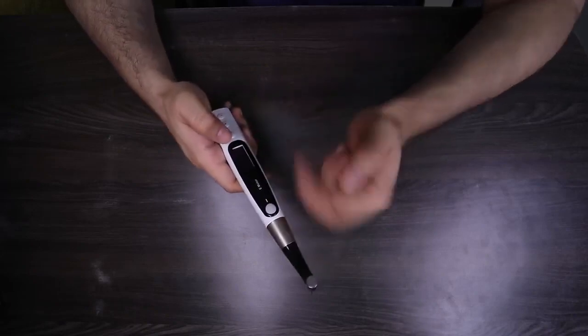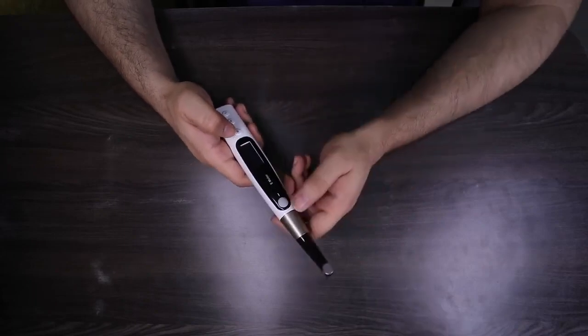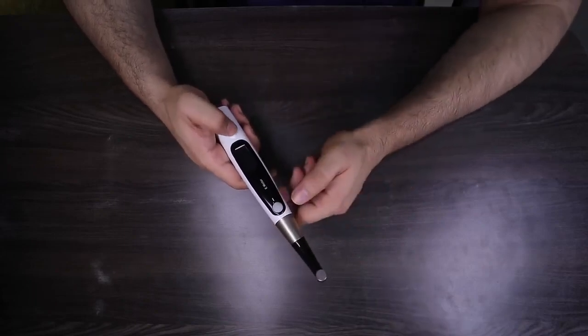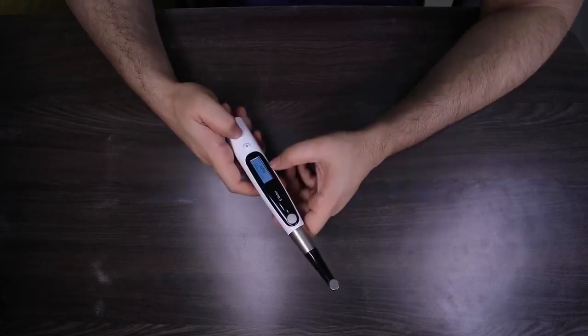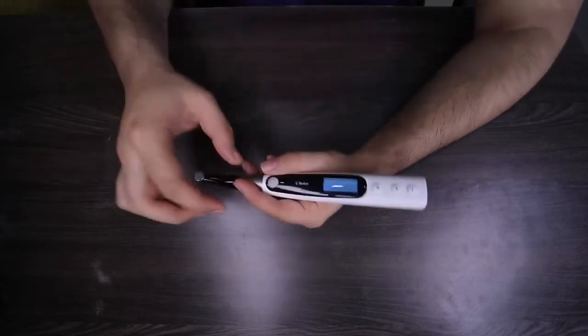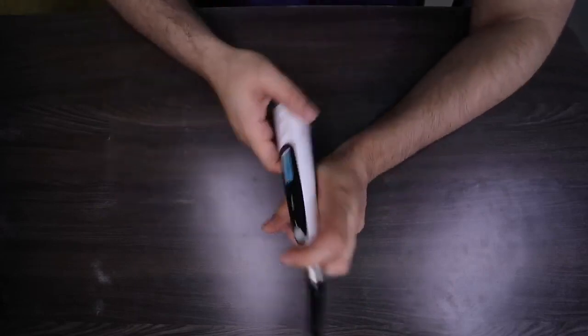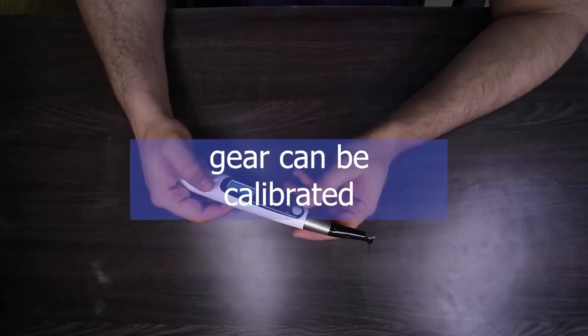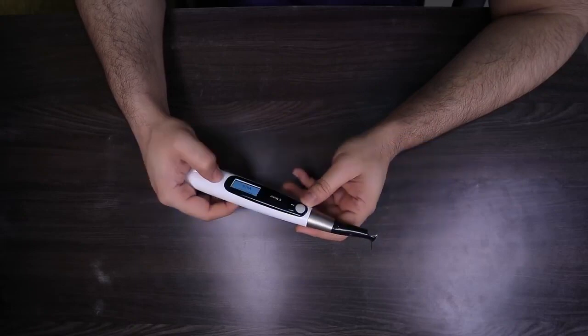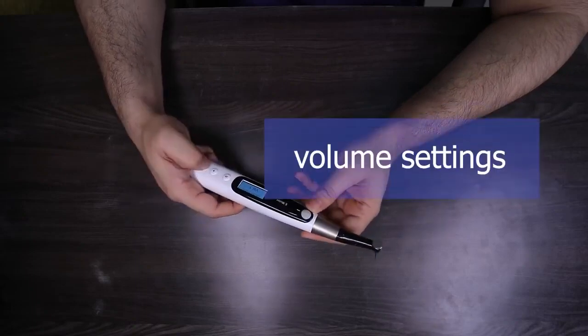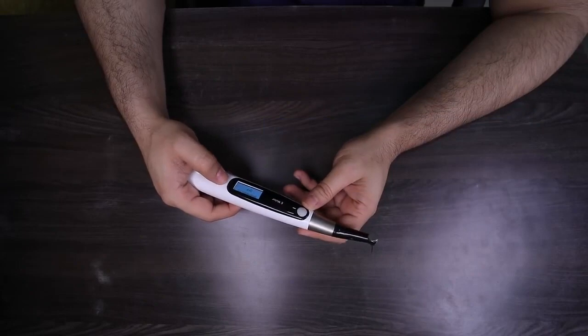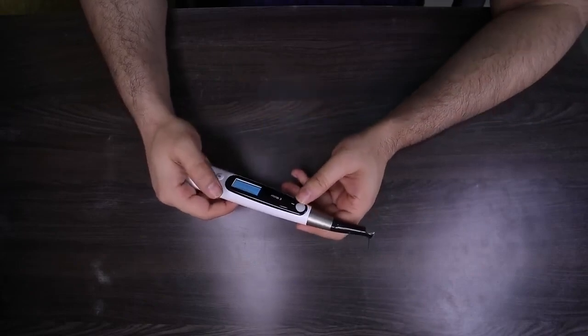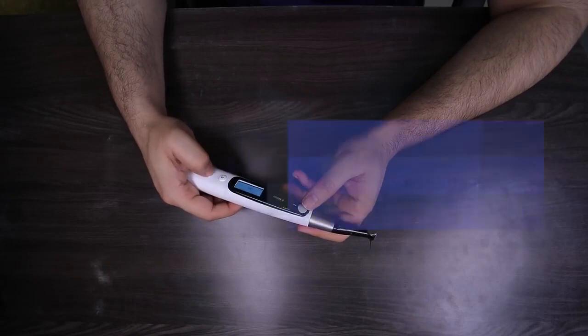Another feature is, if you want to shift between a right-handed and a left-handed operator, you can go into the main company setting by long pressing the S and the power button. You will get the software version. You get to see the dominant hand. You can change your operator preference from right hand to left hand. Calibration, if you want to really calibrate the torque and the gear before you start, you can calibrate the machine, or you can also increase or decrease the beeping volume for your Apex Locator and other functions. And if you want to restore the settings to your company default, you can restore it and it will switch back to its own default settings.